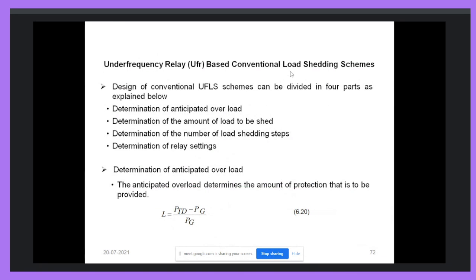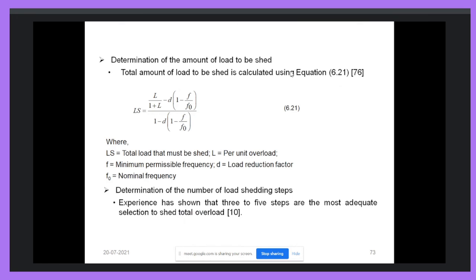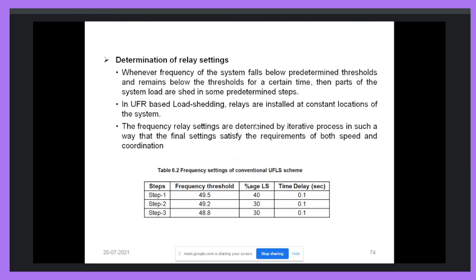And I have compared this artificial intelligence based load shedding with the conventional load shedding system. In a conventional load shedding system, this is how we determine the amount of load to be disconnected from the system. Equation 6.21 is the equation by which we can determine the amount of load shedding required for a particular operating scenario. Here, basically, is the relay-based load shedding technique. In the relay-based technique, we decide the load which will be disconnected in steps: step 1, step 2, step 3. Three-step load shedding is basically adopted in the under frequency relay-based technique, with a time delay.